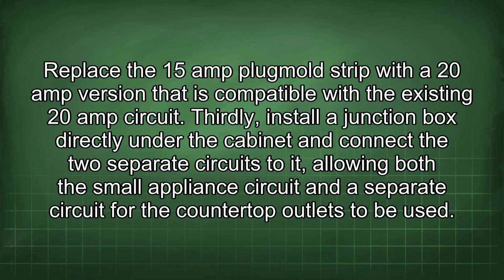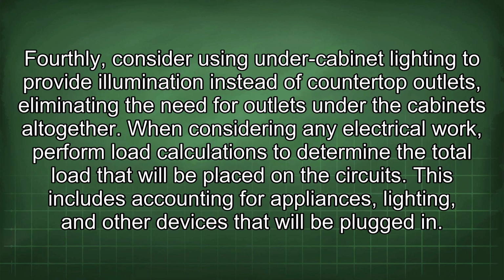Thirdly, install a junction box directly under the cabinet and connect the two separate circuits to it, allowing both the small appliance circuit and the separate circuit for the countertop outlets to be used. Fourthly, consider using under-cabinet lighting to provide illumination instead of countertop outlets, eliminating the need for outlets under the cabinets altogether. When considering any electrical work, perform load calculations to determine the total load that will be placed on the circuits. This includes accounting for appliances, lighting, and other devices that will be plugged in.